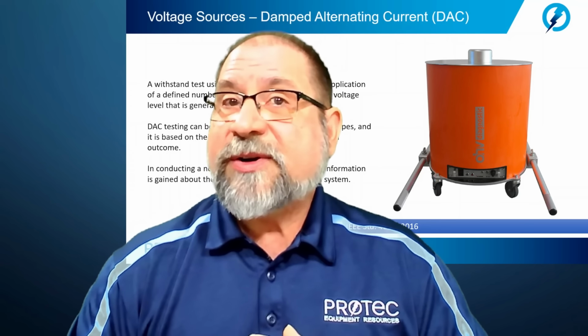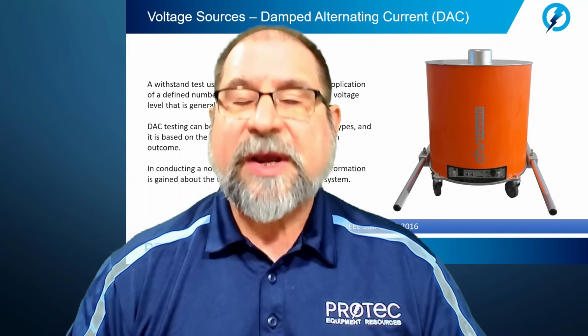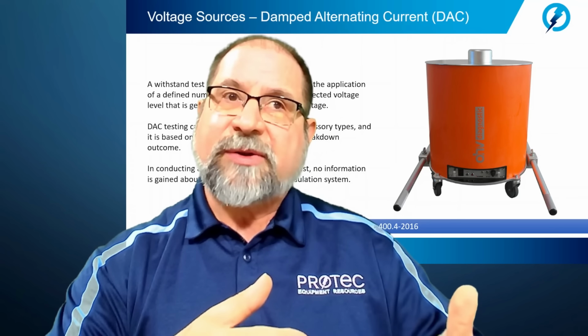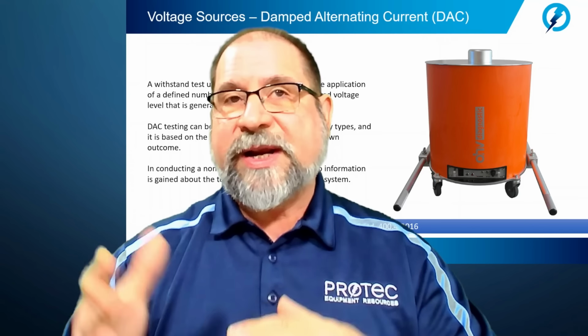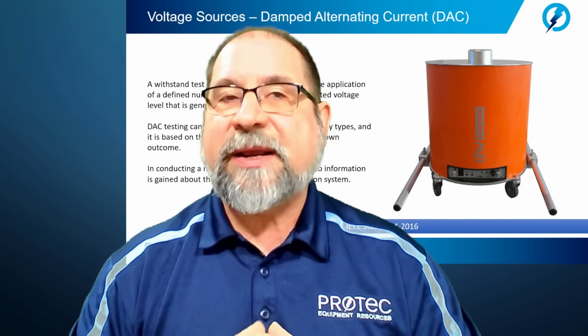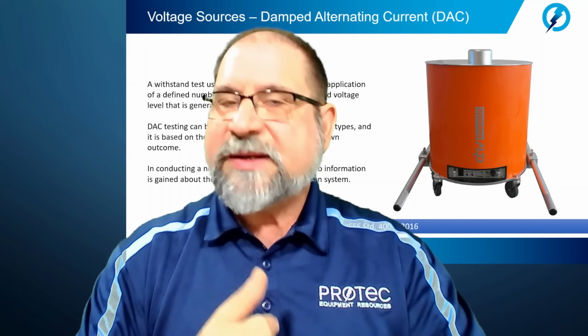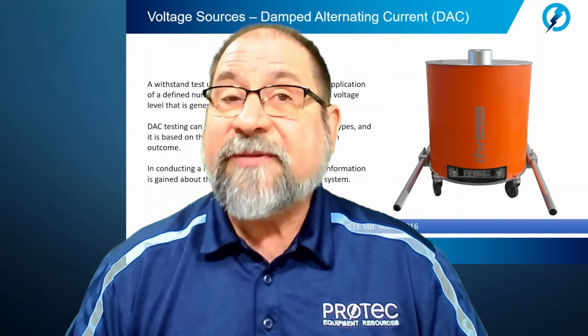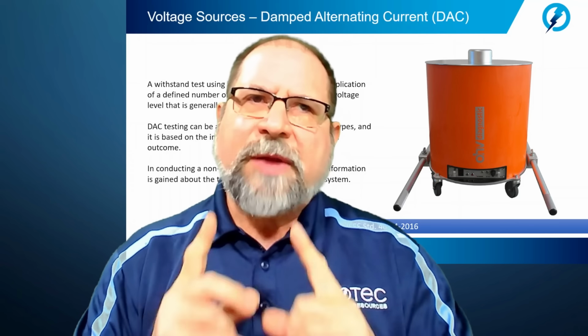Also, we can monitor other parameters such as dissipation factor or tan delta of the specimen. So again, we can combine loss angle testing with withstand testing, where during the duration of the test, we monitor what is happening to the tan delta, the stability of the value. Does it begin to tip up or grow, which would indicate potentially the growth of an electrical tree in the dielectric? So for information on more monitored withstand testing, again, I would refer you back to the webinar that we did on cable diagnostics and testing. And I do believe we cover the concept of monitored high-pot testing or monitored withstand testing in part 2 of that webinar series.